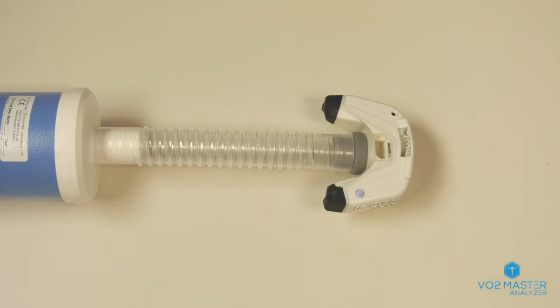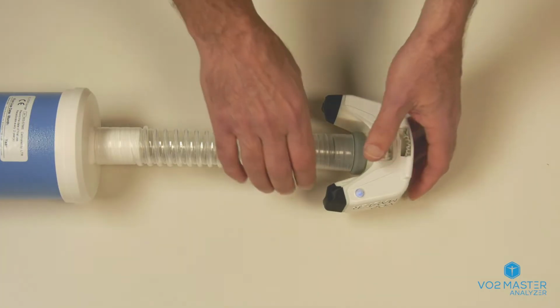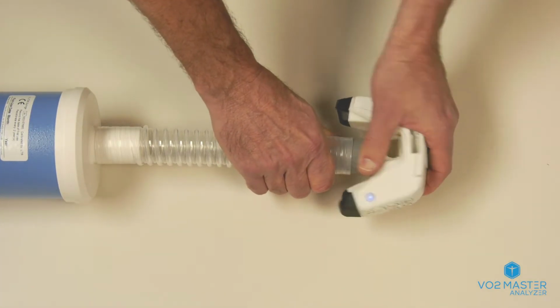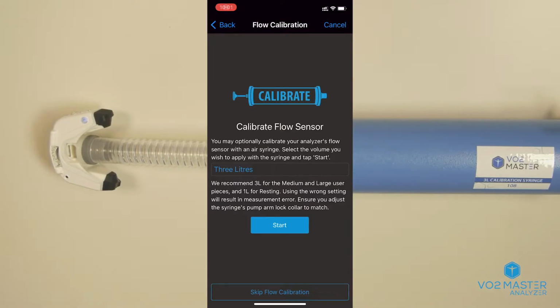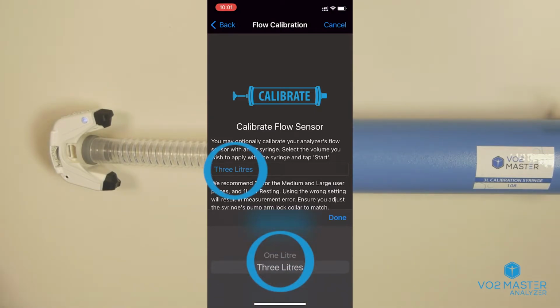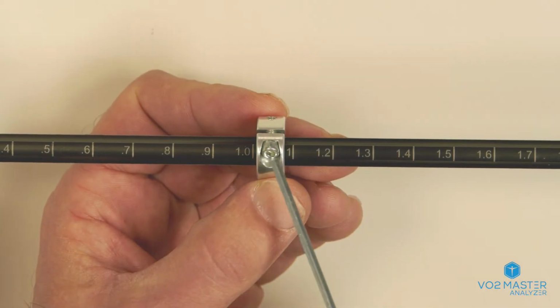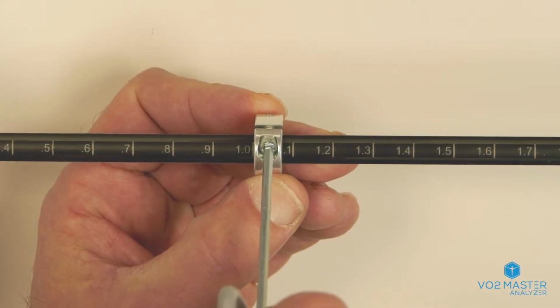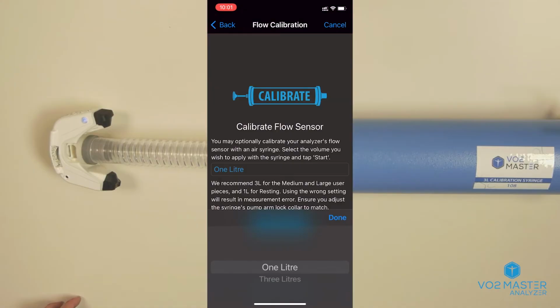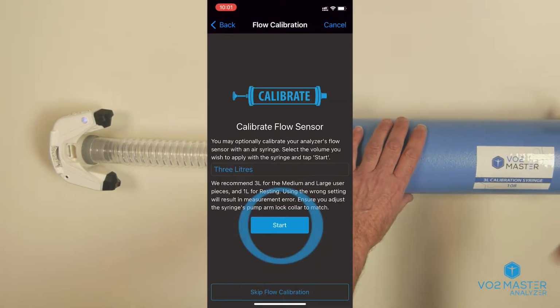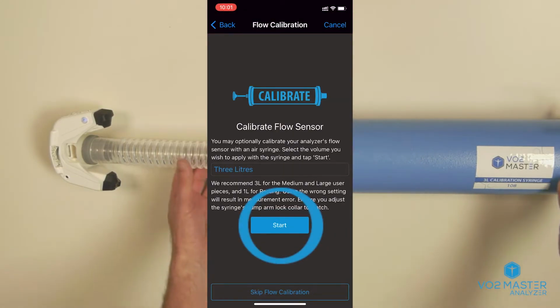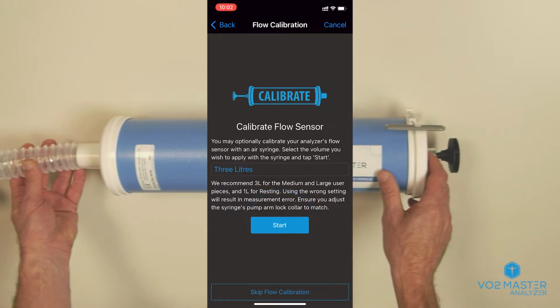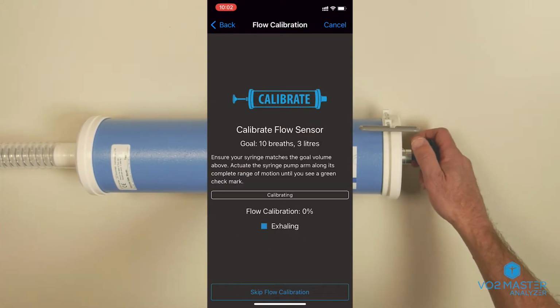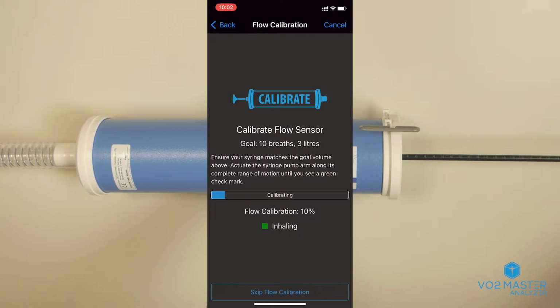When removing the dampening hose, be sure to pull from the end closest to the part you're removing it from so as not to damage the hose. As you're doing a step test, we'll keep the syringe volume at 3 liters. If we were doing an RMR test, we'd change the syringe volume in the app to 1 liter and make sure to slide the locking collar on the plunger arm to the 1 liter mark. With the 3 liter syringe chosen, we'll hit Start on the app and apply approximately 10 strokes of the syringe to calibrate for flow. Try to maintain a frequency of 20 strokes or breaths per minute while calibrating.